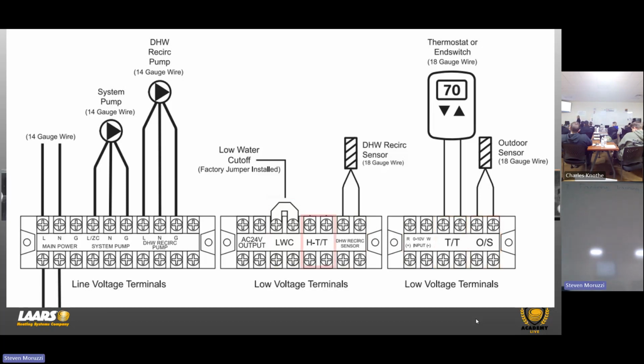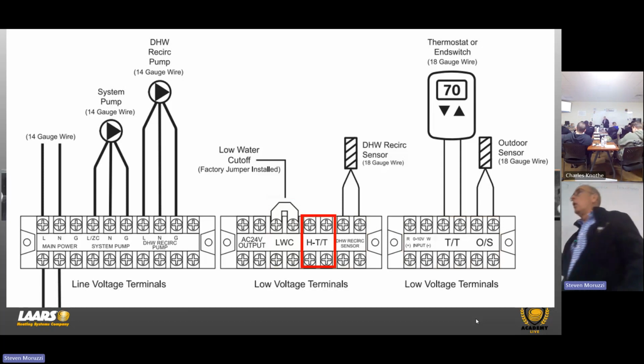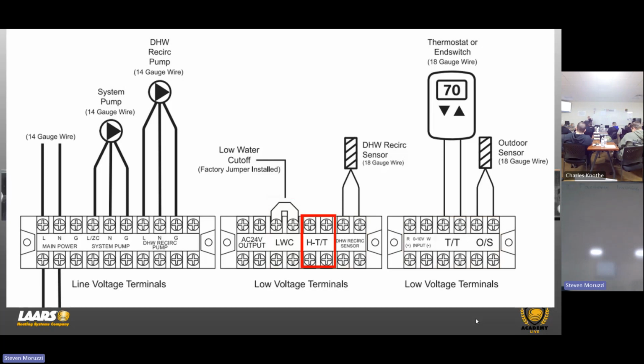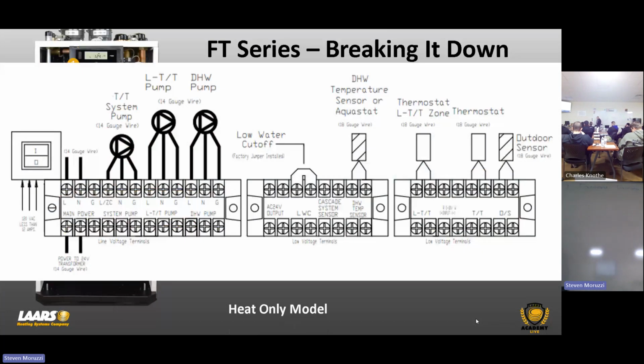So you have outdoor reset on TT. Now, we give you an option here for a high temp zone, okay? Or the holiday mode, okay? And anytime this is closure, we're going to go to full fire. We're going to maintain 180, okay? And this is really designed for a smaller zone. Example of that, maybe there was an old porch that wasn't insulated. They finished it off with some baseboard heat out there, okay? And even if it's 50 degrees, there's no insulation on the floor, they want 180. Or maybe it was a garage and you throw a fan coil unit up inside there. And every time they're running it, they want 180. Anytime we have a TT closure on HTT, we will run full to 180 degrees.